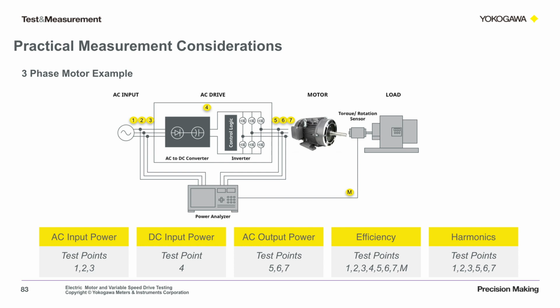For our three-phase motor example, we're going to make connections to our AC drive. So we need 3 voltage and 3 current connections at the input to the drive. For DC input power, we need 1 voltage and 1 current. For AC output, we need 3 current and 3 voltage. So for harmonics, we can measure test points 1, 2, and 3 to see what harmonics are being put back on the AC mains. Test points 5, 6, and 7 will tell us what harmonics were created by the AC drive. For mechanical power and efficiency, we'll need to monitor the motor input at test point M.